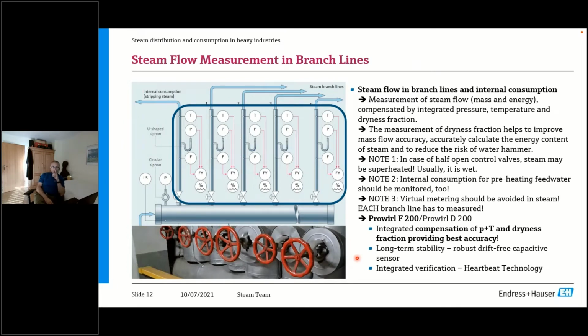When you want to measure the flow to the various points of end use, it's very important that you compensate by pressure and temperature, and that you compensate by the dryness fraction. Why is that important? First, you may have wet steam, because this is the classical case. You have wet steam if everything is working nicely, because you have saturated steam already sitting here, and it's not perfectly dry when you send that to the different points of end use. So you want to know, how much dryness fraction have I got?